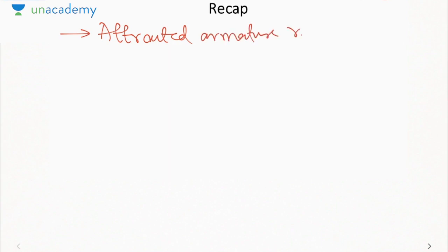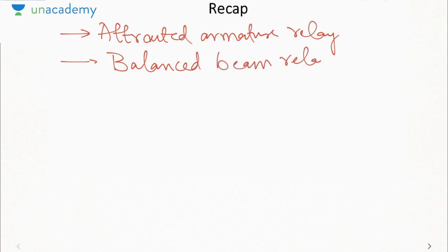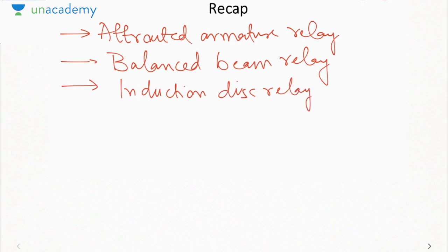The problem with this relay was that the pickup current was fixed, but the advantage was these were the faster relays and they can operate for AC as well as DC. Then we move to balanced beam relay, where this problem was rectified and we can control the pickup current by controlling the restraining current. And then we saw induction disc type of relay, in which we saw two constructions, shaded pole construction and watt hour meter construction.